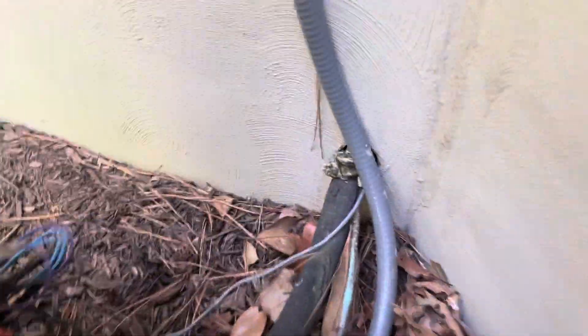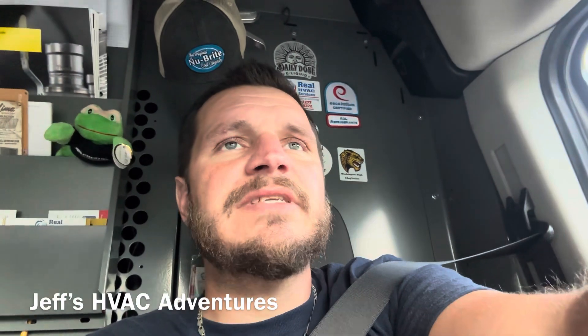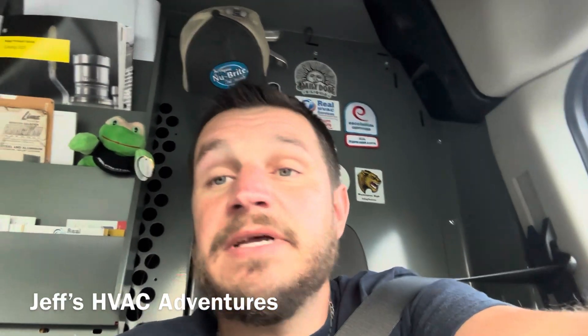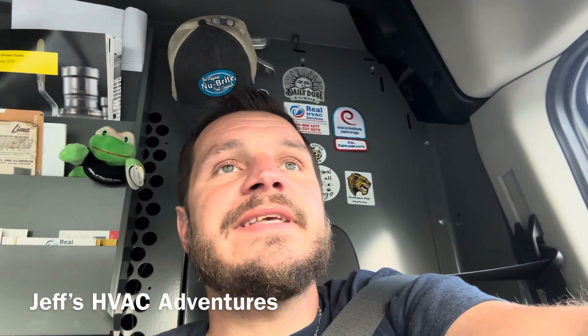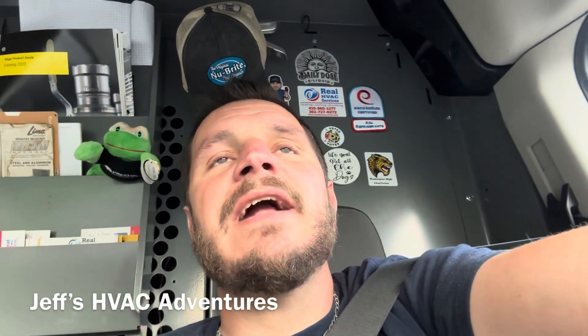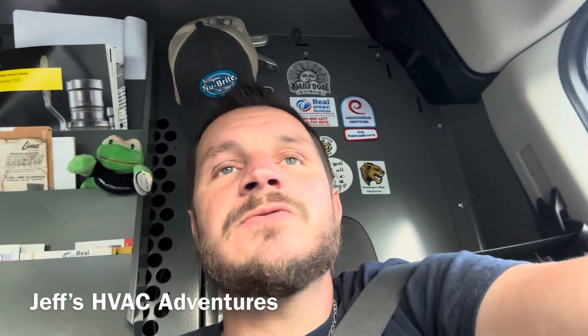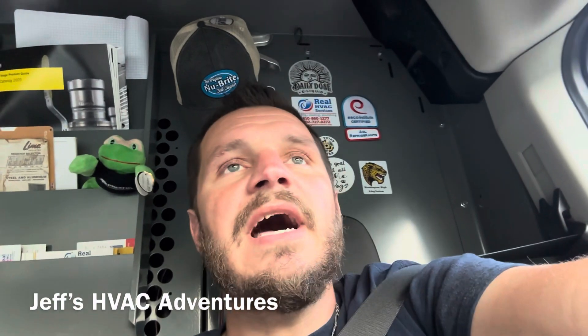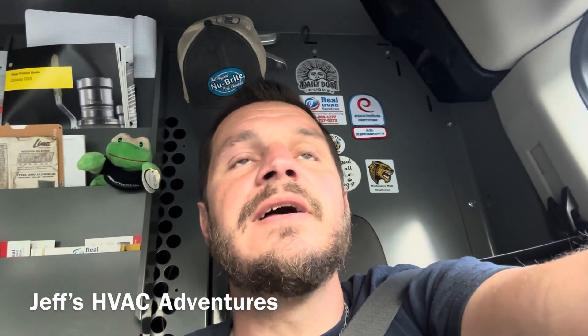She's wound up right nicely in heat. I think I'm going to button this up until we can come back with the right sensor. Hey guys, sometimes we've got to do what we've got to do to get our customers by. A 10K sensor is a 10K sensor - some look different, some are for different things, but at the end of the day they all work the same. It's just at what scale it reads at. I usually keep a 10K sensor on my truck. That one was an outdoor temperature sensor, but it works. After letting it run in heating for a while, I checked the thermostat and it was actually reading in the 50s in heat mode. So it is working and it'll get them by.